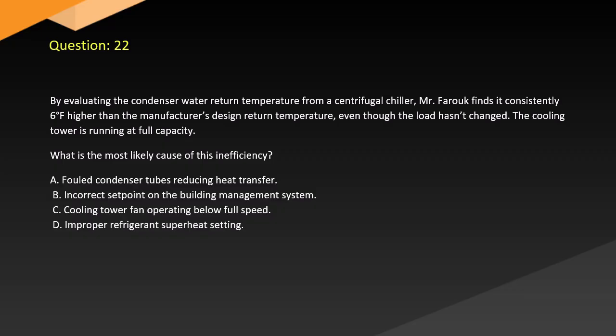Question 22. By evaluating the condenser water return temperature from a centrifugal chiller, Mr. Farouk finds it consistently 6 degrees higher than the manufacturer's design return temperature even though the load hasn't changed. The cooling tower is running at full capacity. What is the most likely cause of this inefficiency?